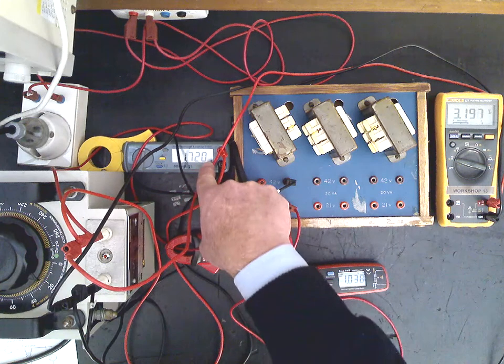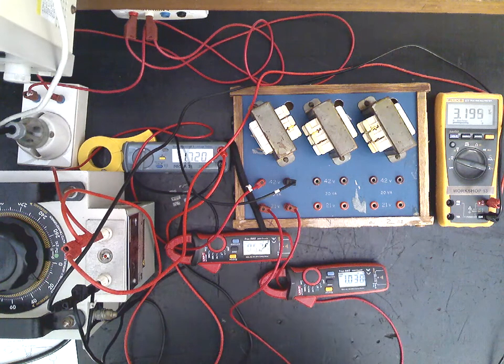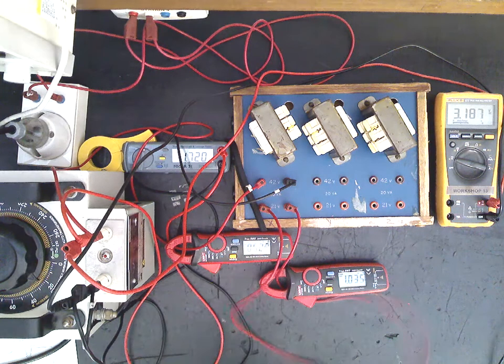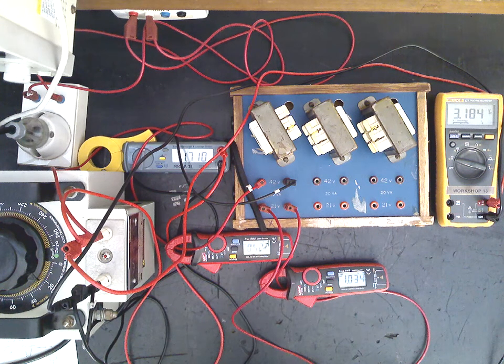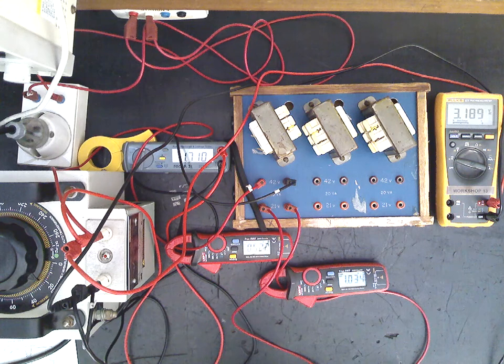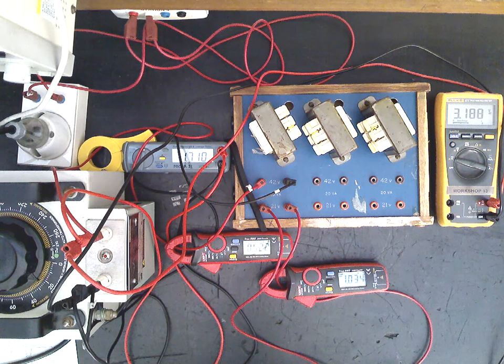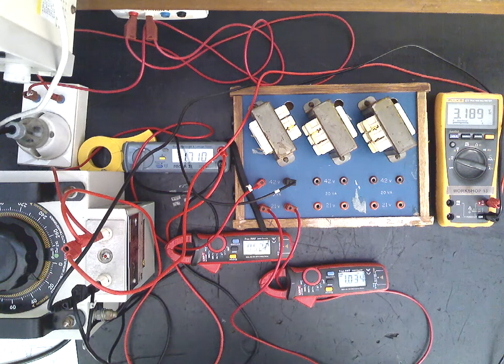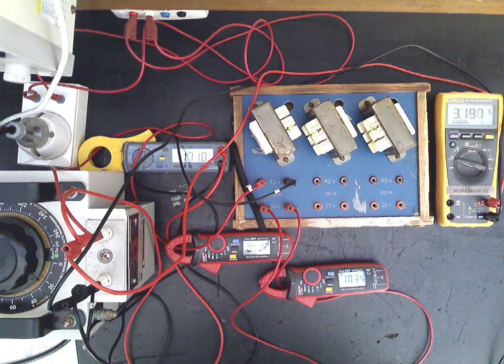And the power loss up here in the primary on the short circuit test is 1.7 watts. So it's the sum of the iron loss power and the copper loss power that adds up to the total losses in the transformer when it's under full load. And we can calculate that efficiency of the output divided by the input.